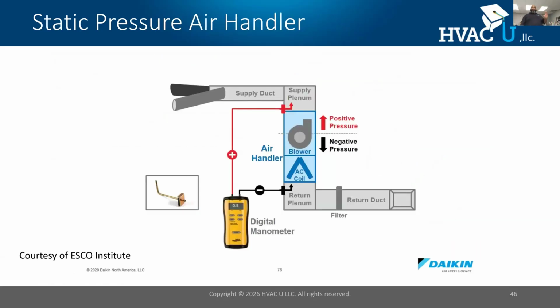This is a furnace. This is an air handler. Now, with an air handler, the coil is integral. It's installed at the factory. So since it's shipped that way, we include it in our static pressure measurements. Depending on the manufacturer, it may or may not have a filter that you need to account for also. With this measurement, notice how the blower and the AC coil are within the static pressure probes. I will take this information, and this has a different static pressure requirement because the coil is integral. So this is an air handler.